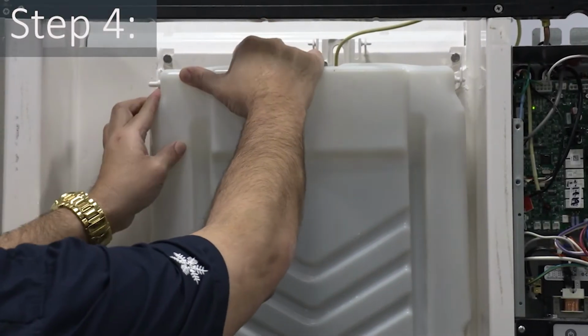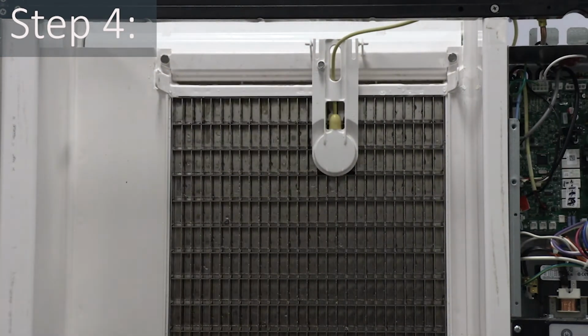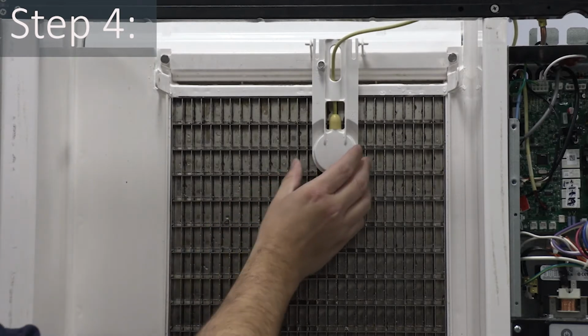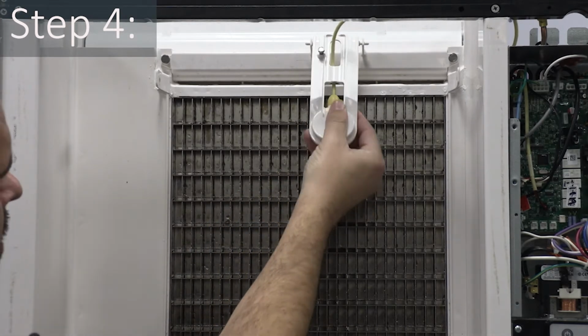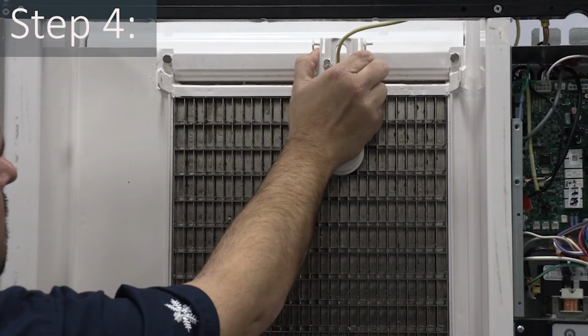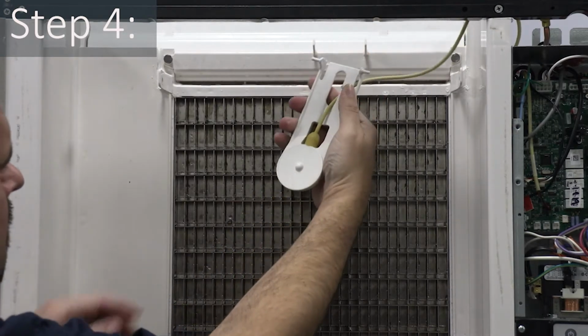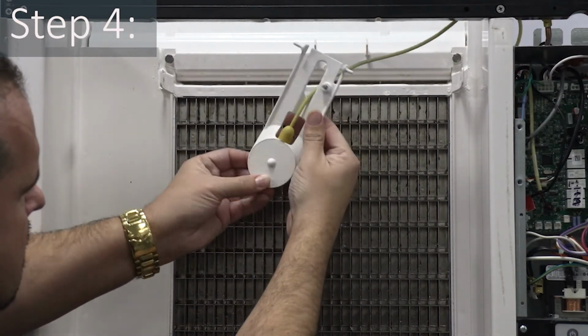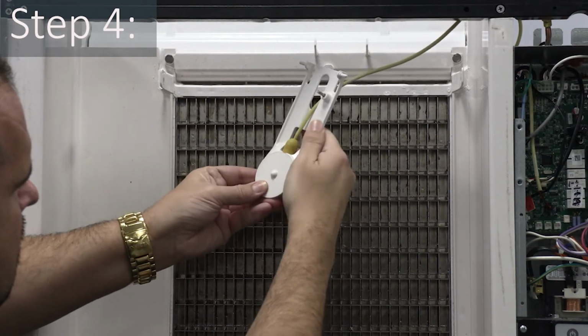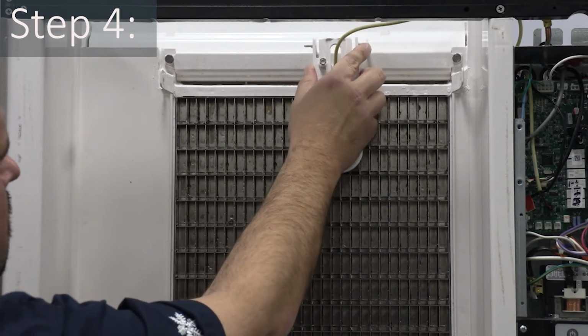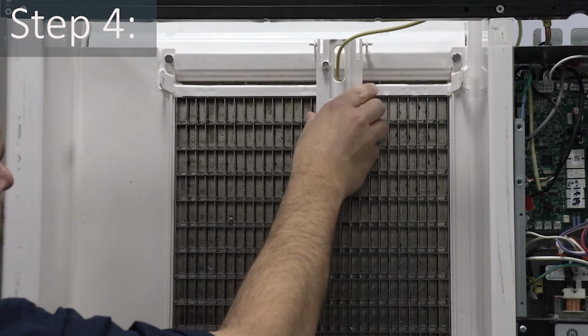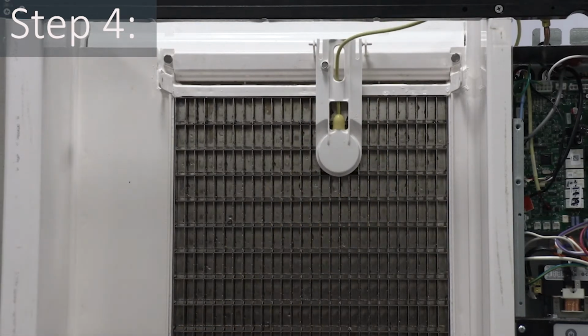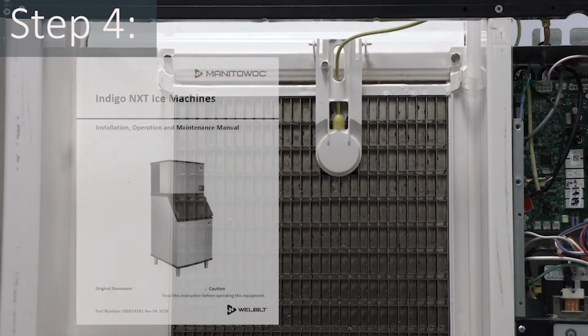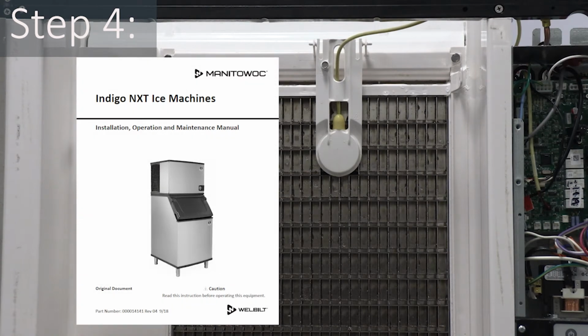Step 4. Inspect the ice thickness probe, referred to as the ITP, for any physical damage. On the face of the ITP, look for bulging or cracks. Also, look for deformed pivot pins and/or pivot pin arms. The ITP is not dishwasher safe, meaning high temperatures can warp the ITP. Follow the cleaning procedures outlined in the Install, Use and Care Manual.